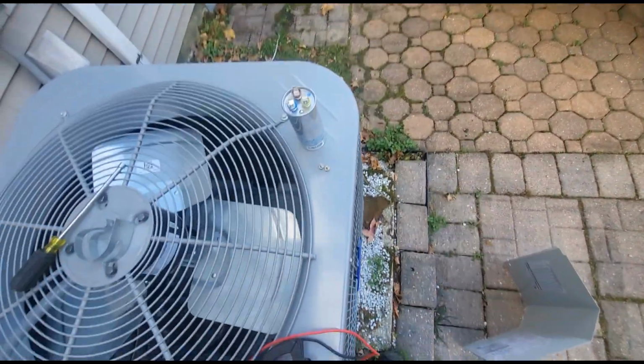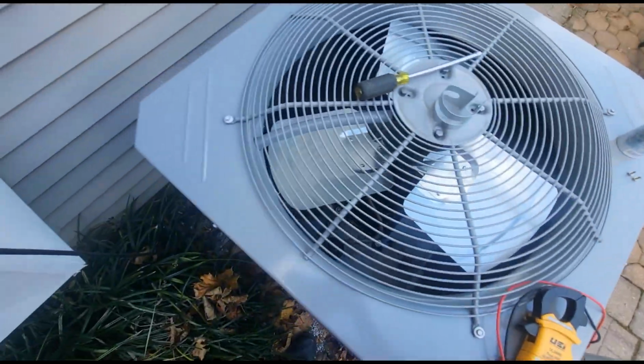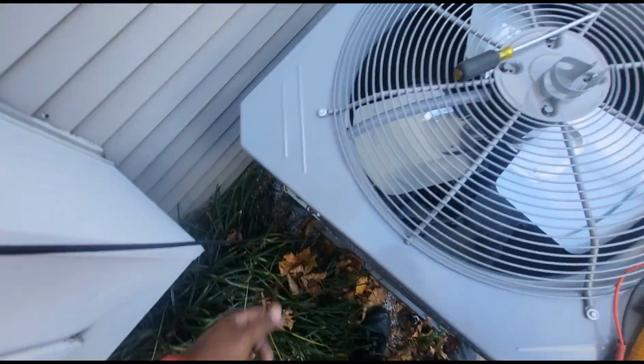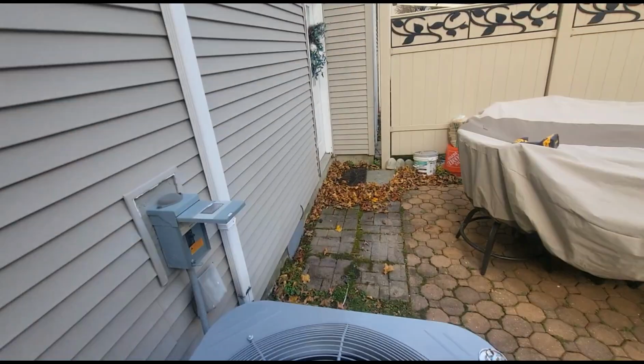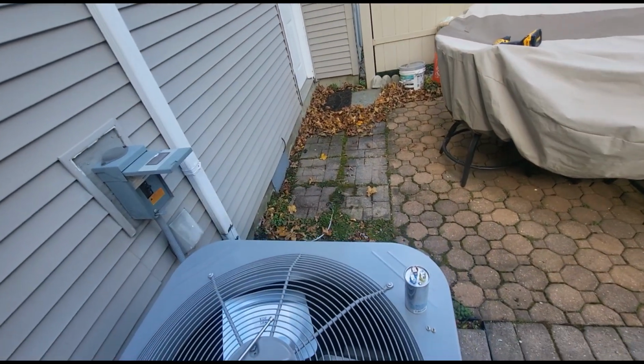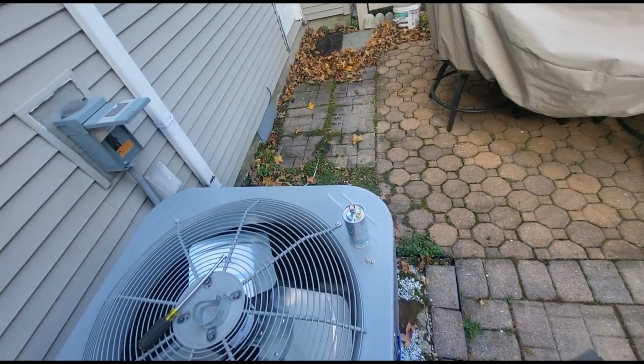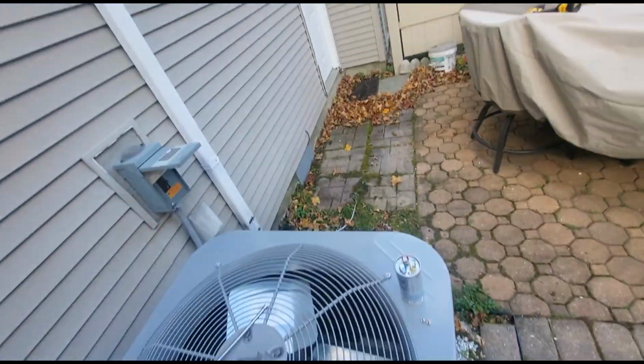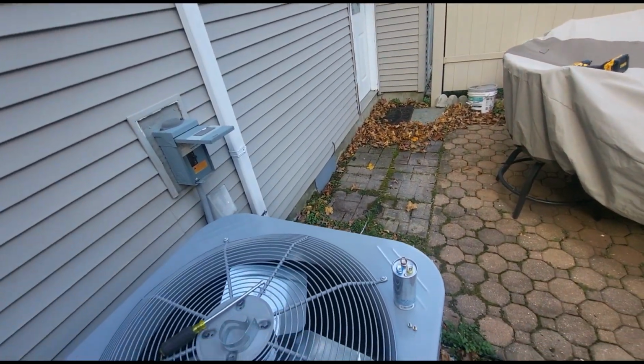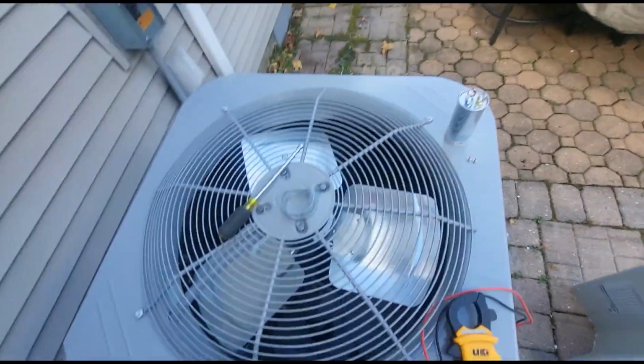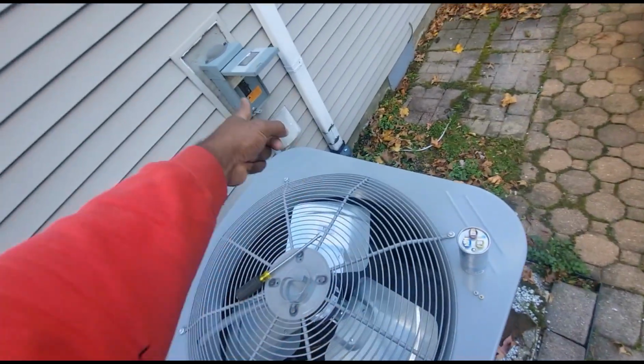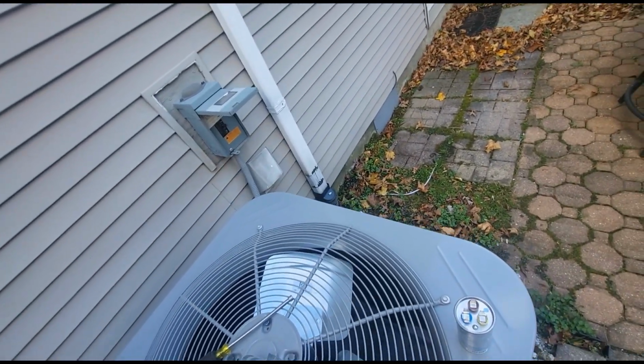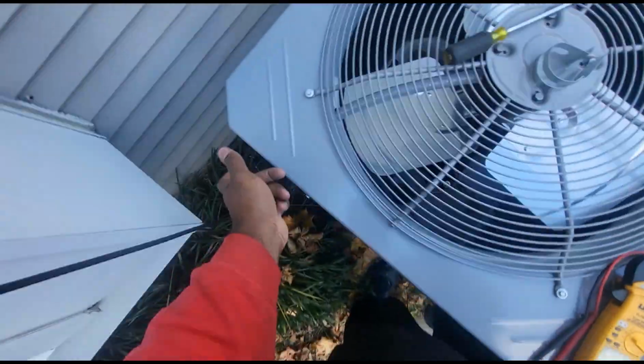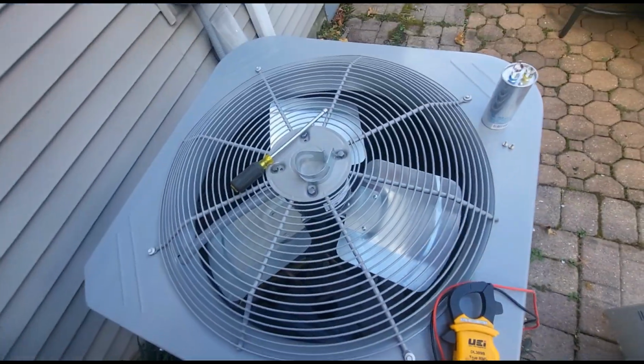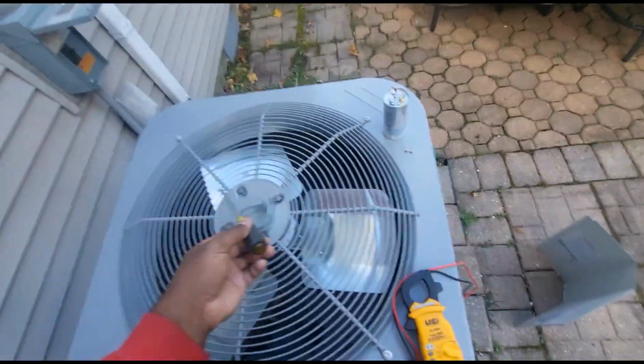But guys, what I'm gonna do is put this capacitor back in, and I'm gonna check my defrost board. And also, by the way, I got my thermostat off. The house is already up to 72 by now. I know it probably would have been up to 75, 76 degrees. So I gotta put this back in, and once I turn the thermostat back on, I gotta wait for the time delay on the stat, and I gotta wait for the time delay on this defrost board. All right, guys, let's get to it.